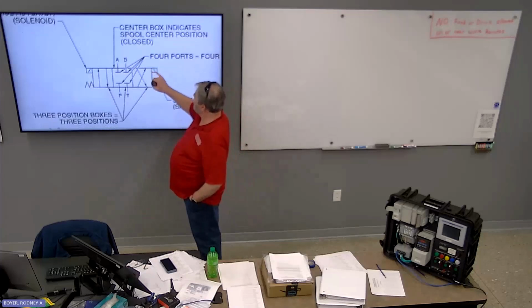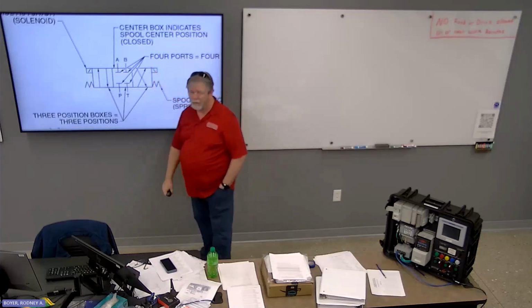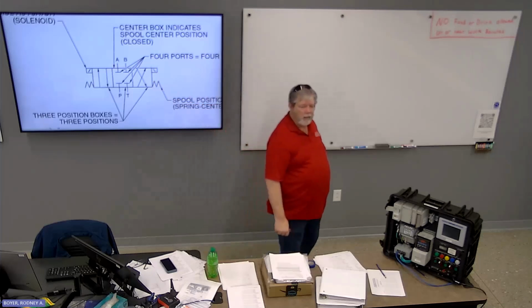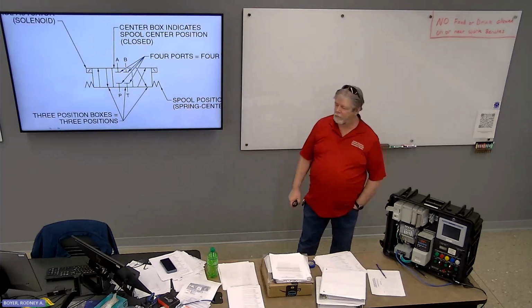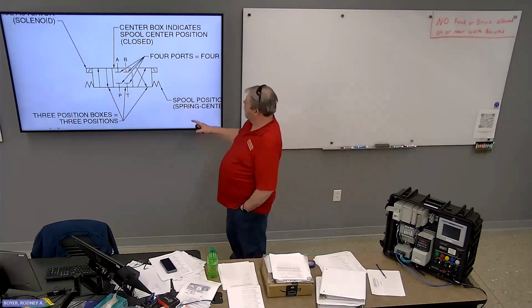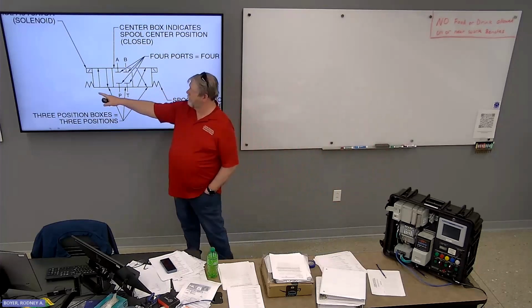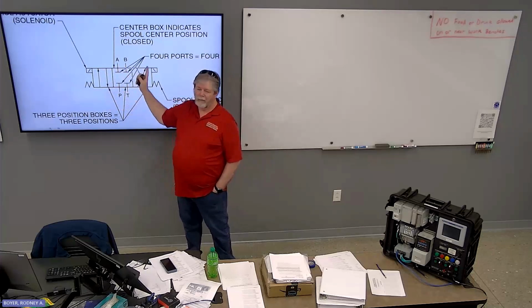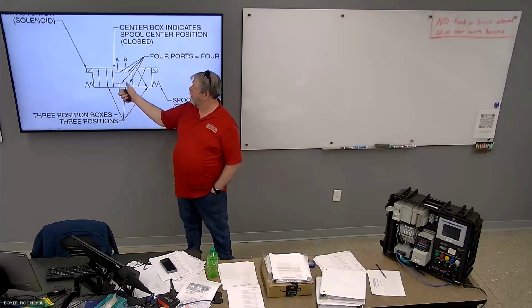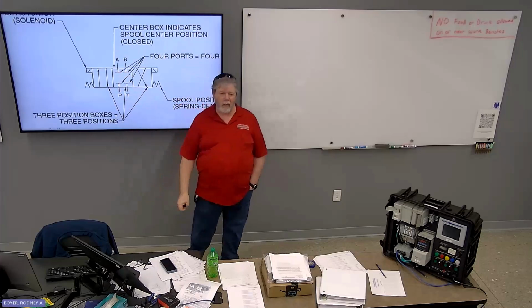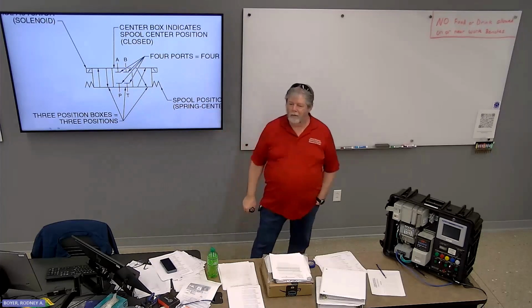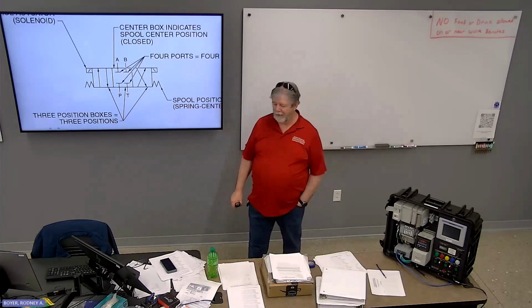Okay, the box with the slash in it means it's solenoid operated. Okay. Spring. So it's solenoid operated both directions, with spring return to center. APB center, all ports blocked. 3-position 4-way. Be a 3-4. 3-position 4-port.